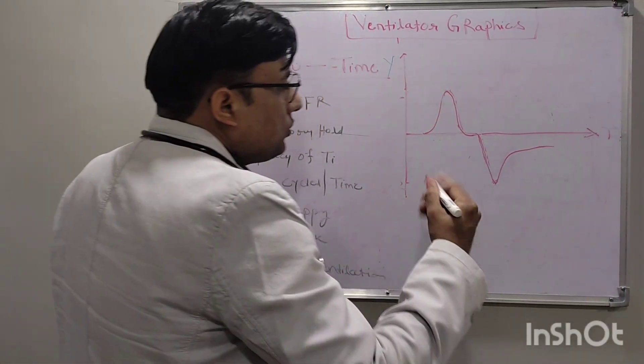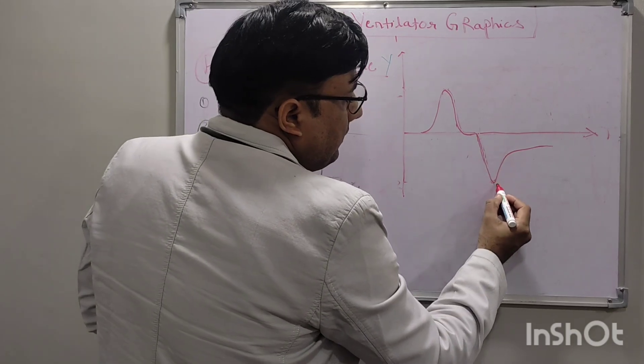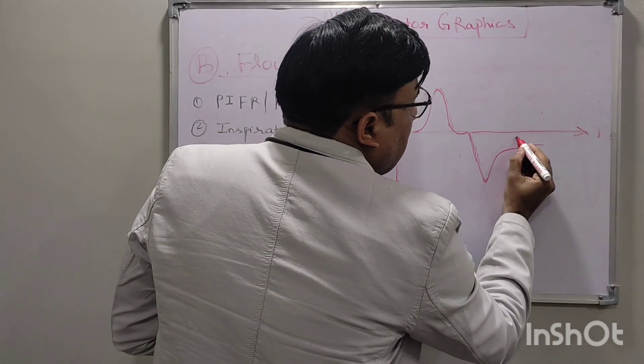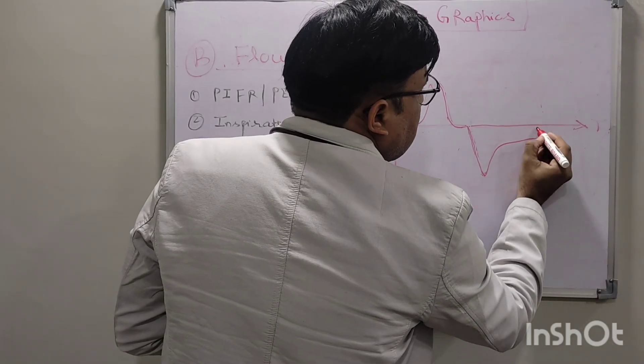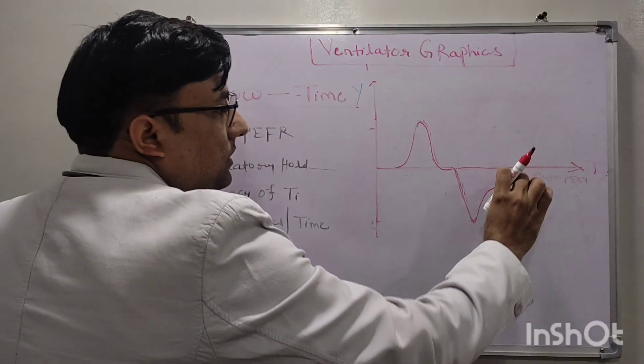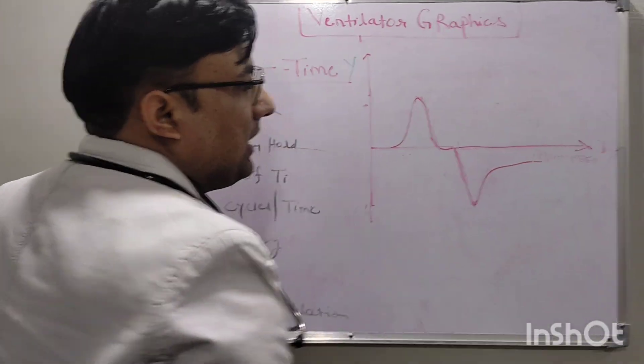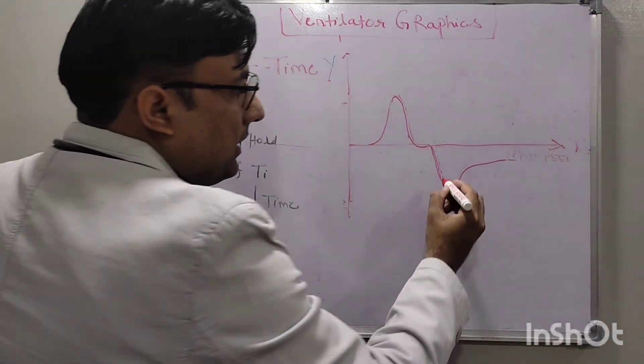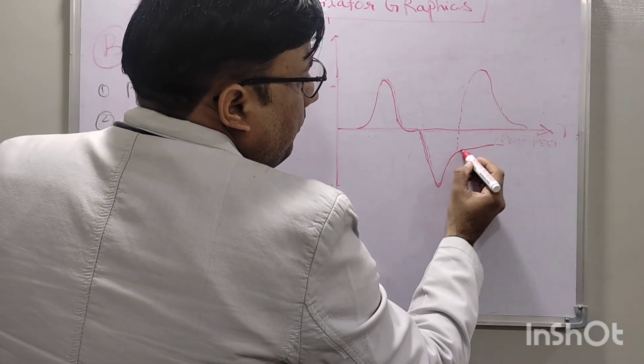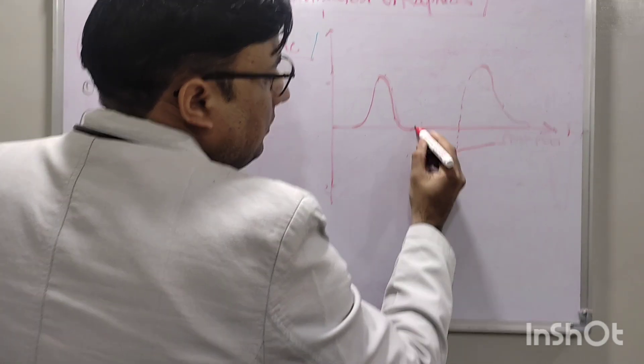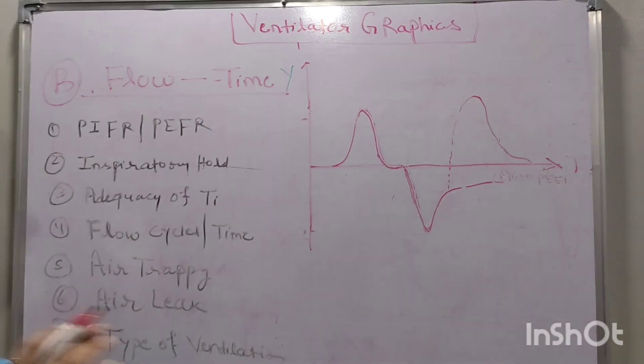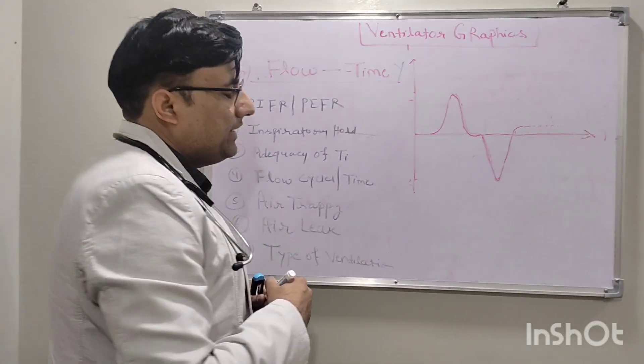We can also see air trapping or auto-PEEP in this graphic. The expiratory flow should return to the baseline, but if air trapping or auto-PEEP is present, the expiratory flow will not reach the baseline. The amount it fails to reach the baseline indicates the degree of auto-PEEP. In the actual ventilator graphic, the next breath cycle starts before the expiratory flow returns to the baseline — this is auto-PEEP.